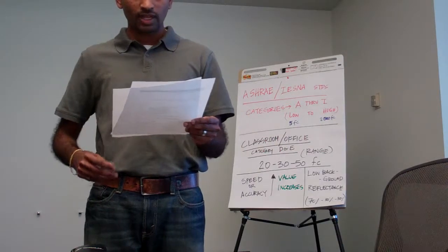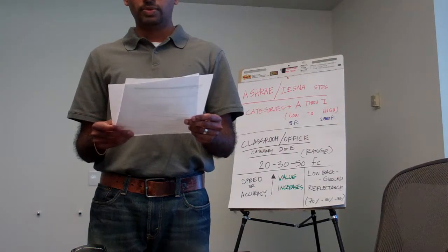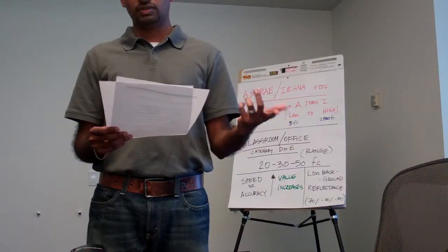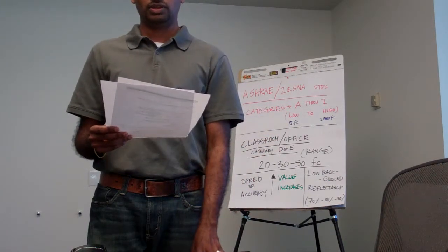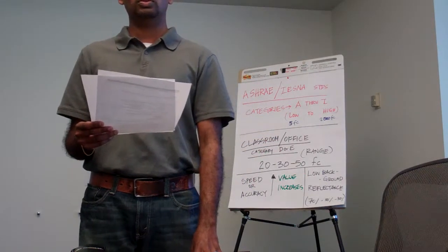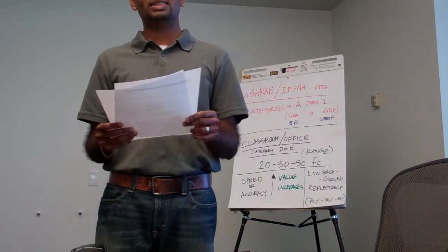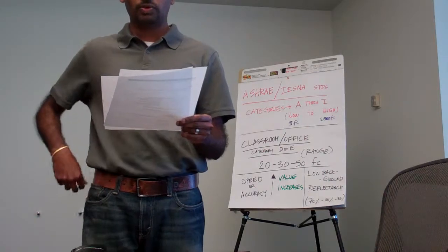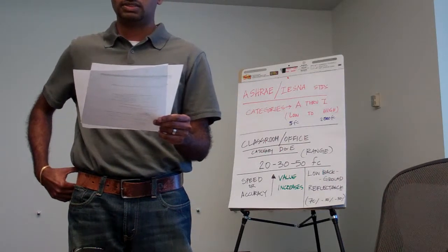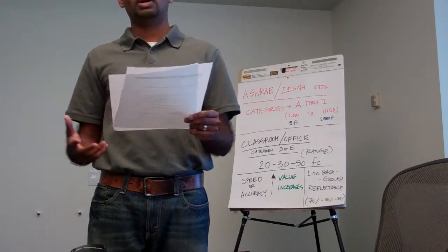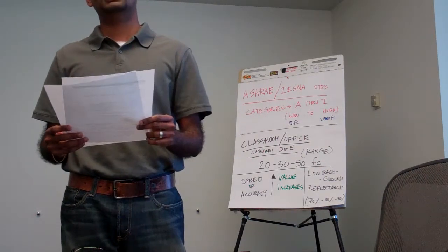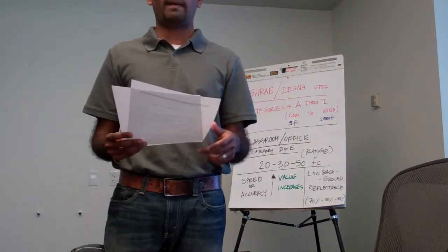When your school district wants to open the gymnasium to the public or other events during all weekends and holidays of the year, which of the following would you do? B. Correct. And the reason is, we want to provide a complete dedicated HVAC system for the gymnasium for energy reasons and controllability reasons.